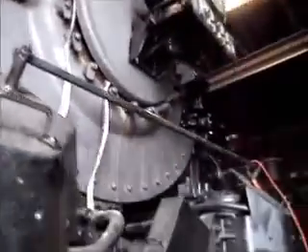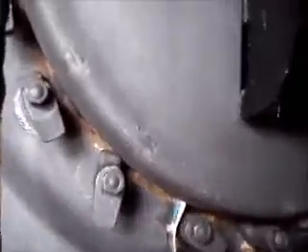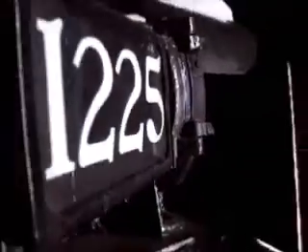We went inside the smoke box up here and cleaned that. It's actually opening up here. In here, you can see in here. I actually can see the plain plates and cleaned off pretty good. No longer all flaked up. I tried to brush it out and vacuum it as much as possible. Last time they did that, I don't think they did as well.